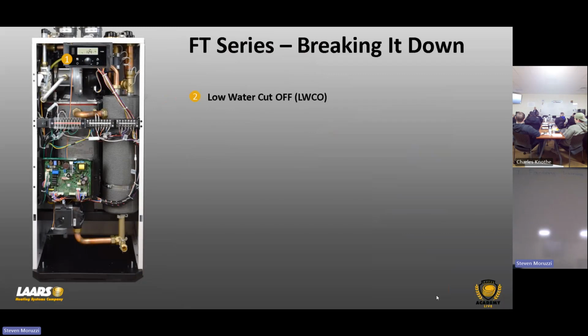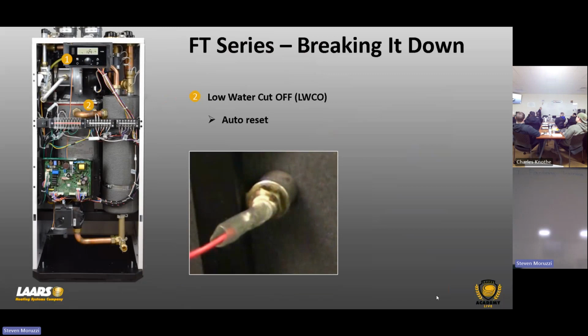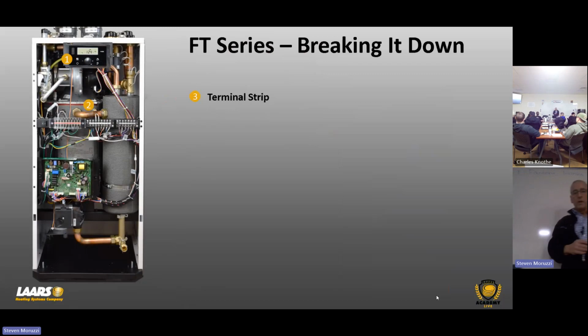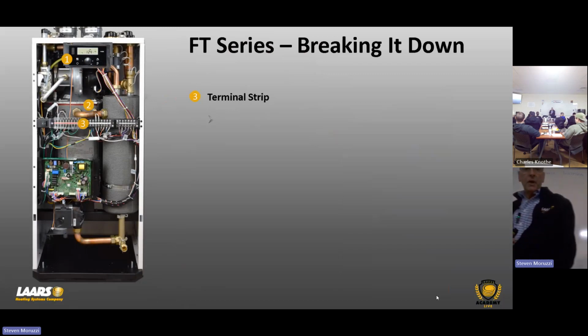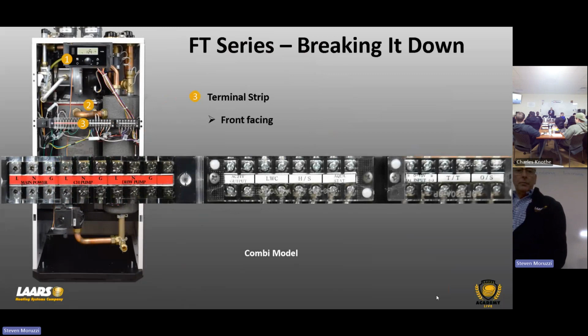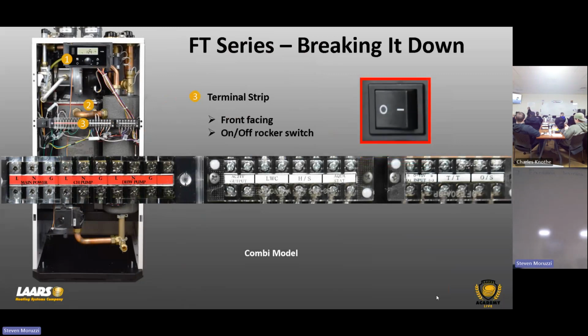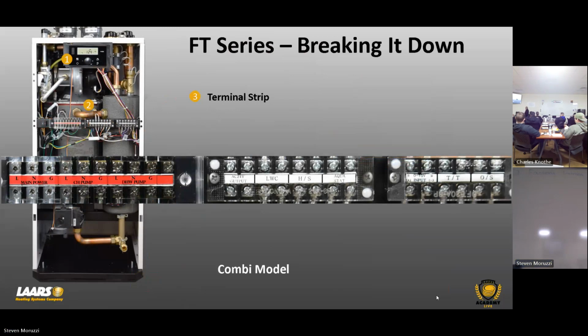And we also have the diagnostic codes. We still have that built-in low water cutoff right there inside that cabinet. And again, that's auto reset. So in here in New York, where you're required to have the external one, keep that in mind. So your terminal strip is right here, front facing. So here we have on the left, don't forget that on-off rocker switch, which is right there.